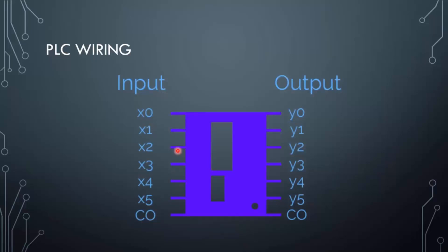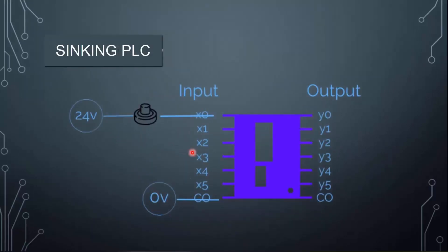So first let's see the input wiring for the PLC. There are two types of input wiring. The first is when the PLC is sinking: 24 volts is connected with one of the inputs and the common is connected with zero volts. The PLC is said to be sinking because the current flows into the input. The push button is said to be a sourcing switch because it is sourcing the PLC.